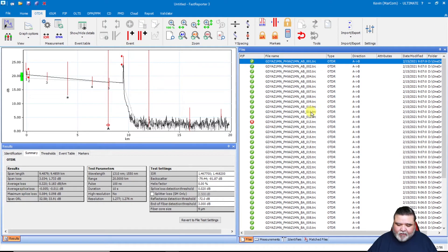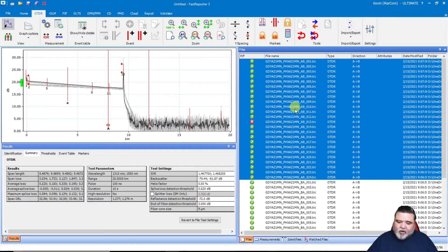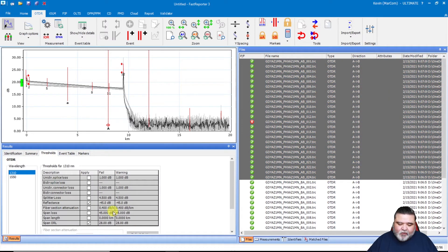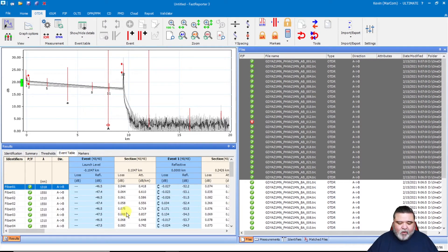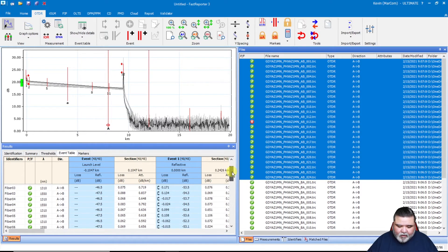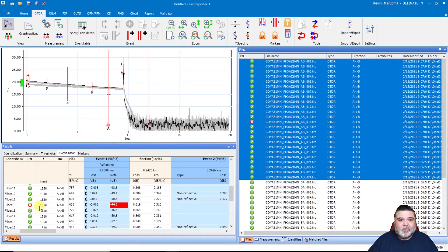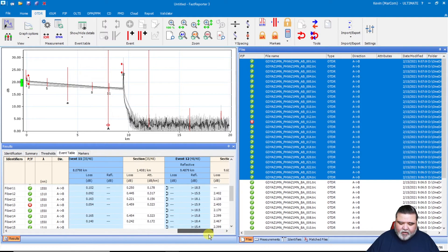I select the first fiber, highlight it, hold down shift, and select the last one — number 24 — which highlights all one direction. A good naming convention that sorts alphabetically and numerically makes it a lot easier to manage. I look at everything here to confirm it's all the same — 100 nanoseconds, 10 seconds, everything looks good. Then I go to the event table and check the thresholds to confirm they're locked in. I can see we have a global pass/fail and there's a fail — we'll have to look and see what's causing that. Scrolling down, we have a failed reflection at the patch panel on fiber number 13. It just barely fails at the negative 45 threshold.